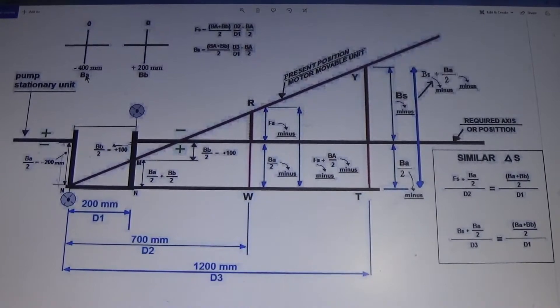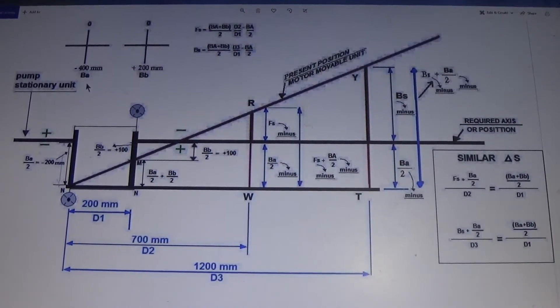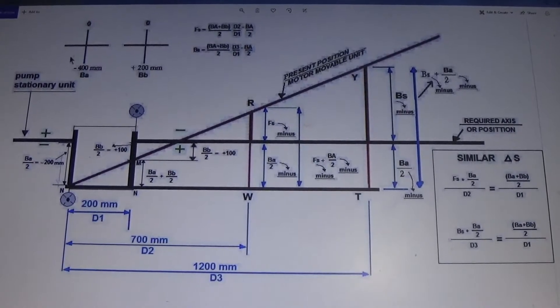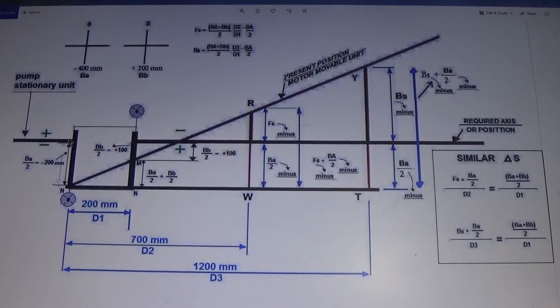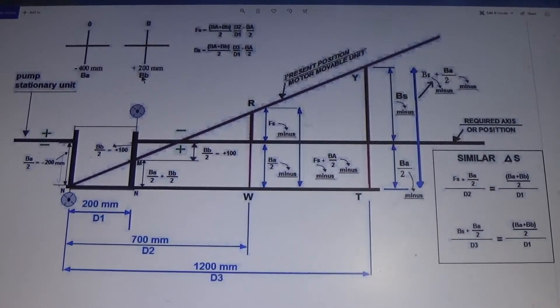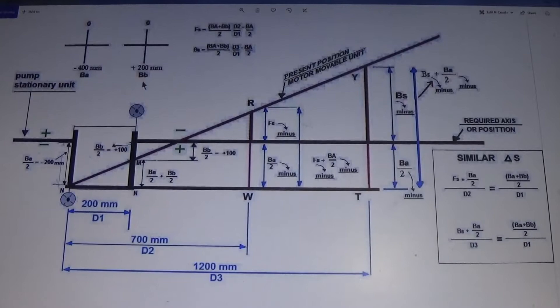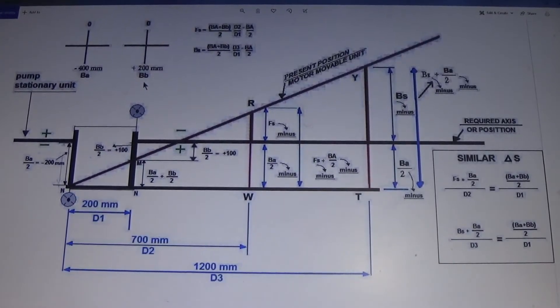BA is the reading which you take on the pump side. You make it zero at the top, then you go down and you find BA at the bottom. Similarly, BB is the reading taken on the motor side — you make it zero at the top then come to the bottom. This is for the vertical direction formula, and the same formula can be used for the horizontal side also.